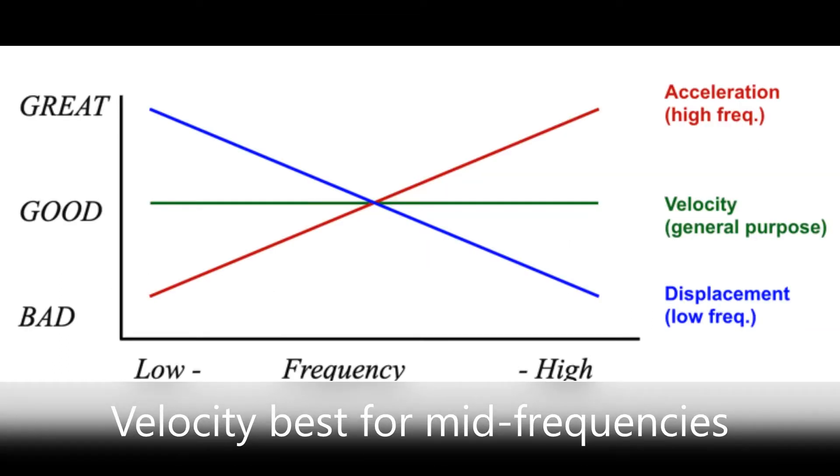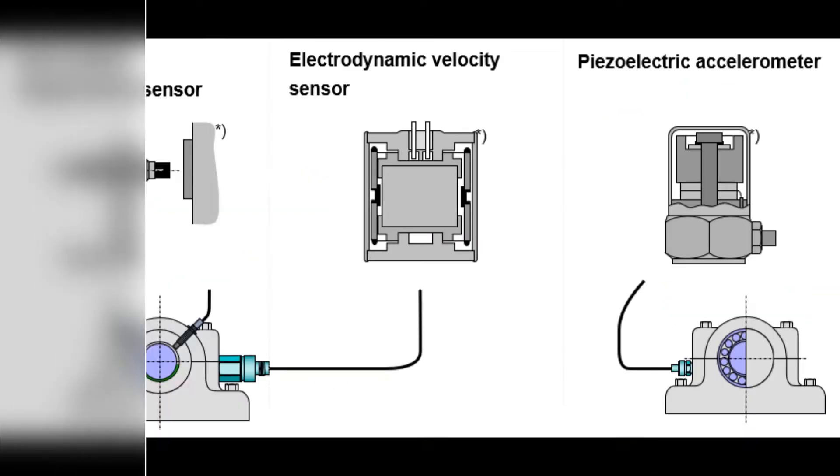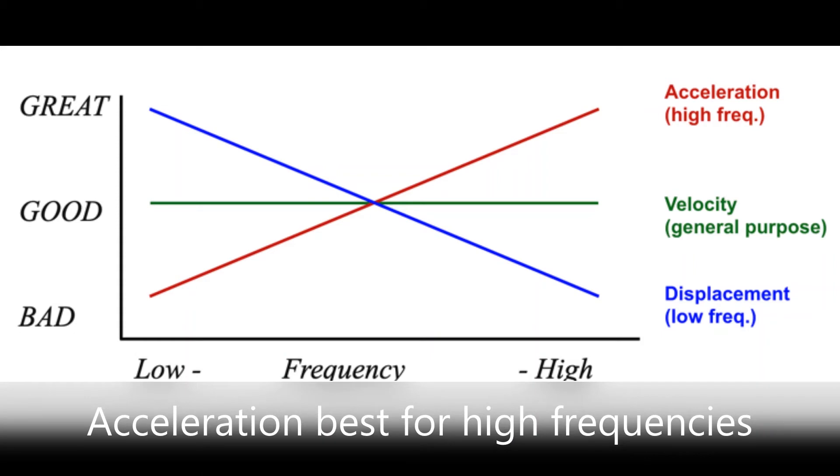This is the most common for most standard rotating machines. Number three: acceleration is the change in velocity over a given time, often measured with an accelerometer. No moving parts, stable over many years, which makes it the best sensor. Acceleration is best for measuring high frequencies. This is common for looking at early warning of roller bearings.